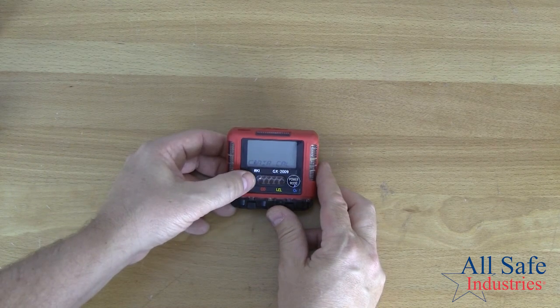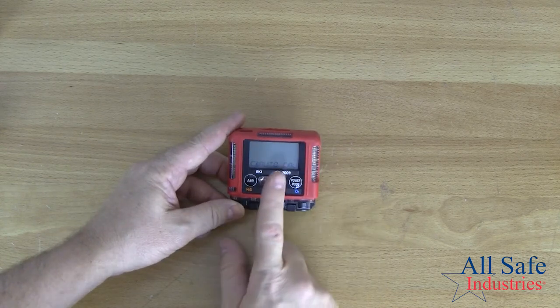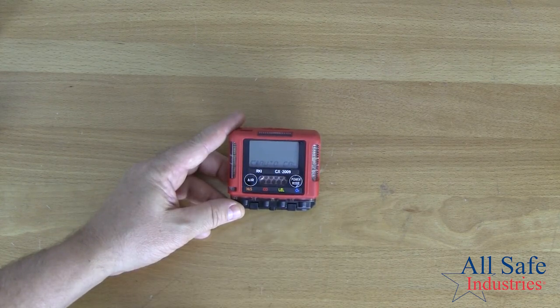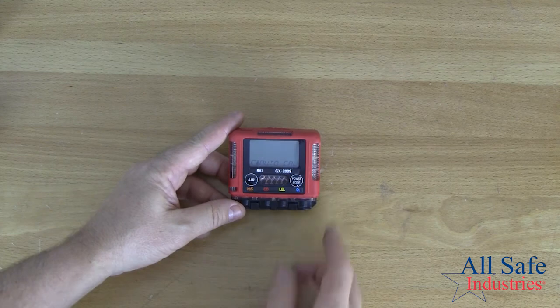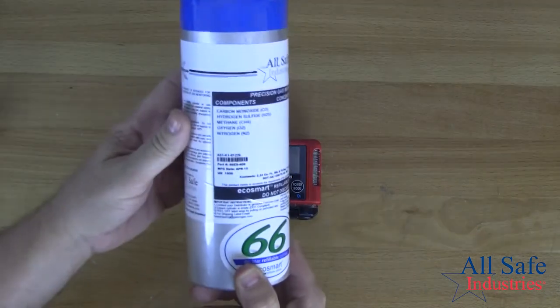So I'm going to use my air button to scroll to the next menu. And this is my auto cal menu. This is how I automatically calibrate my sensors. Now in order to do that, I need my other accessories. I need my cylinder of calibration gas.